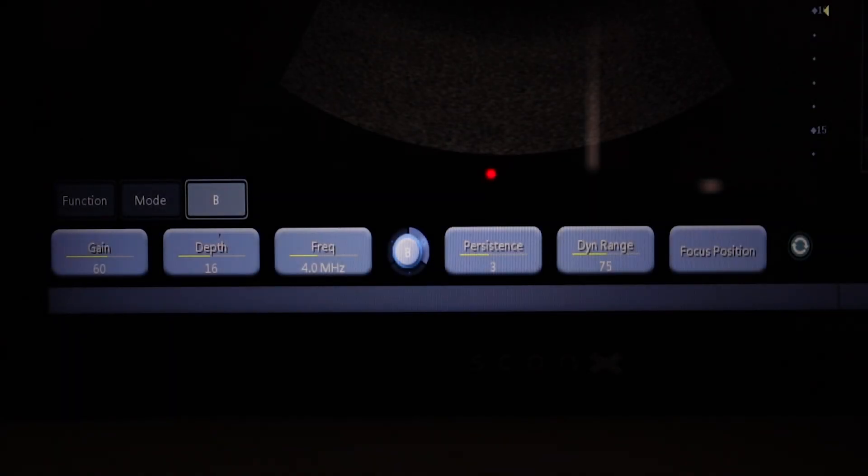But what we will do is show you how to turn it on and off on the system. So to change into harmonic imaging, first of all make sure you are in your standard B mode application. The B will be highlighted here. This is just your standard application for 2D imaging.